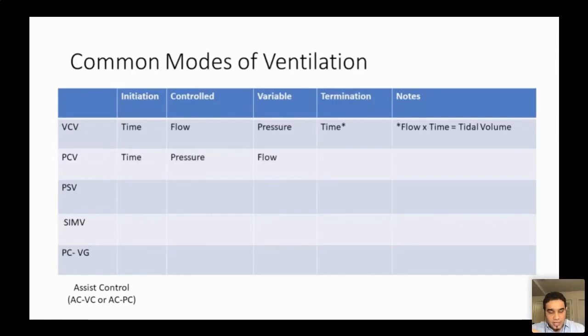In this mode, we control the pressure, we leave the flow variable, and we terminate with time. Here we do not adjust the tidal volume because we are not setting a volume. We're basically adjusting a pressure set.